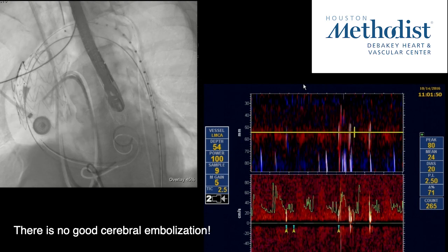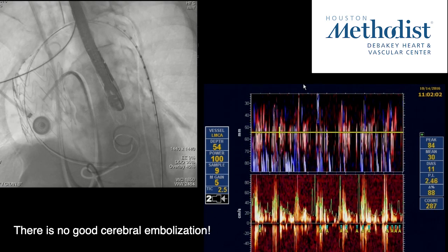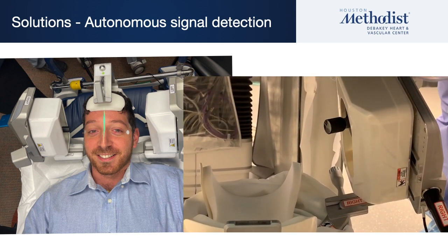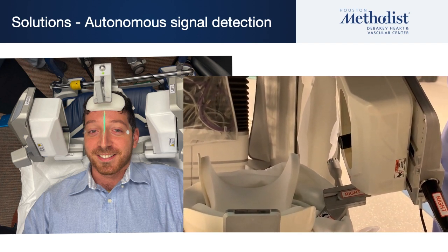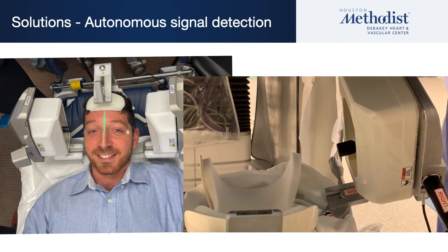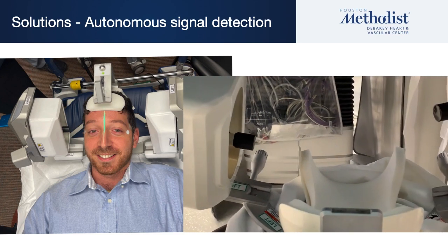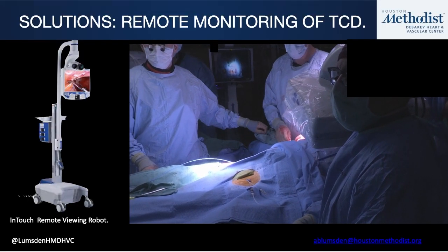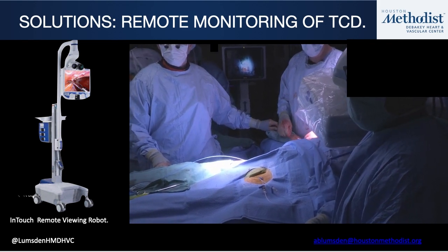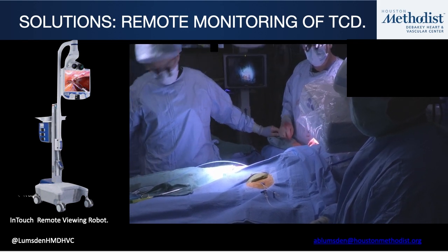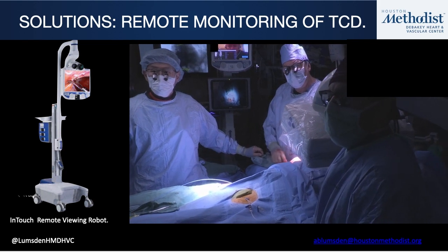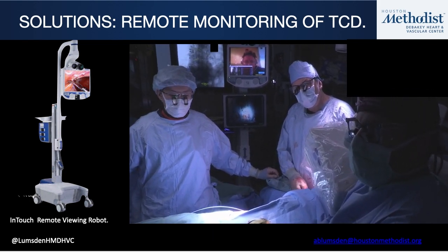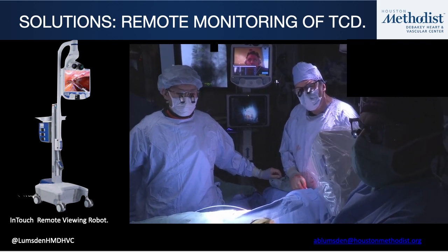Two problems we discussed are the lack of expertise in interpreting TCD and who's going to put the probes on. We have two potential solutions. One is this robotic transcranial Doppler system where the probes autonomously engage the hemisphere — actually faster than manually doing this — and then track throughout the course of the procedure. So for those who don't have this expertise, robotic TCD probes can acquire the signal autonomously. In terms of interpretation, this is how we've done it: performing a branch graft while a colleague monitors remotely by sending the TCD signal through an in-touch remote viewing system. There are now many different companies looking at remote monitoring. He's telling me when I'm causing embolization and I can try to modify my technique if at all possible.